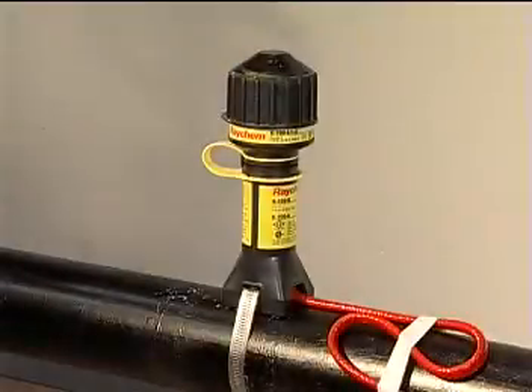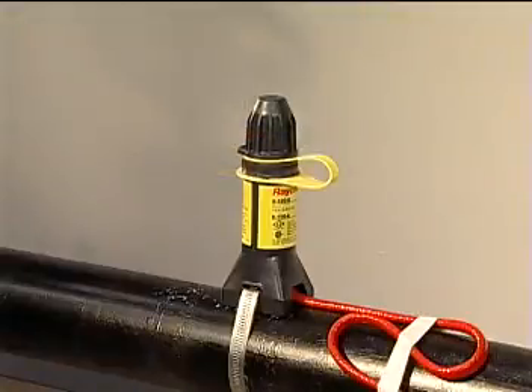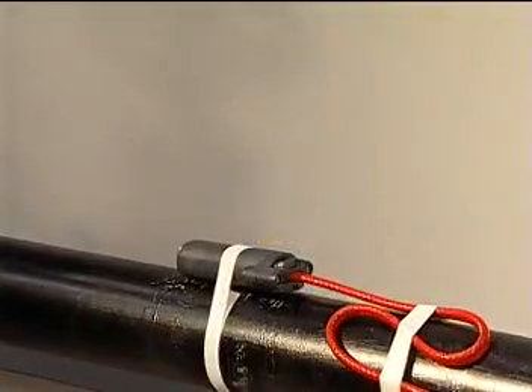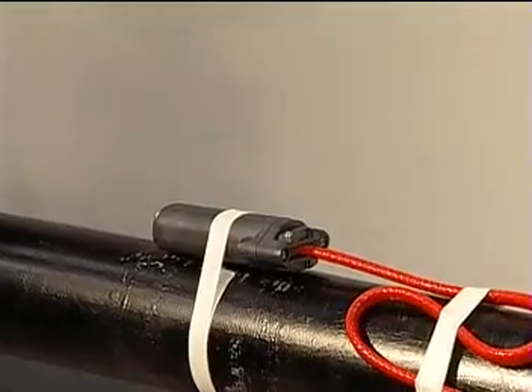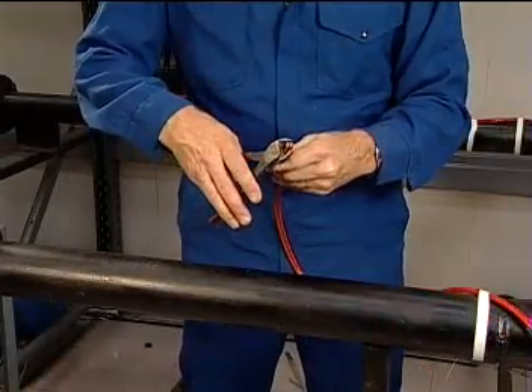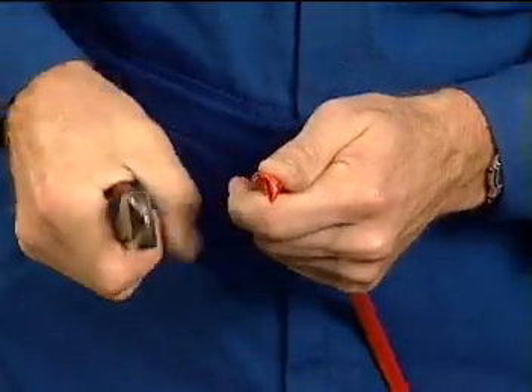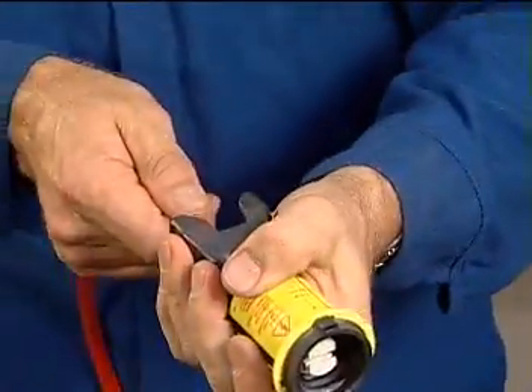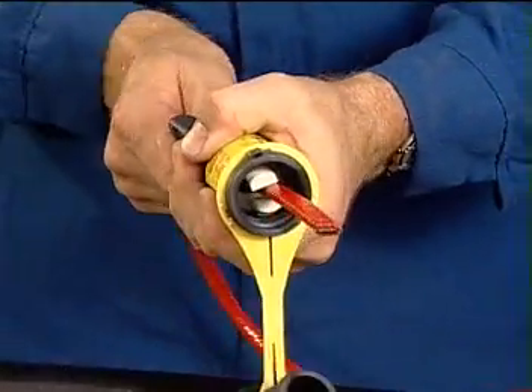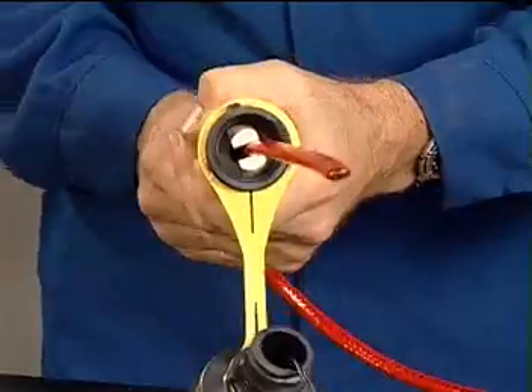Use an end seal to terminate a cable at the end of a circuit. There are 3 types available. Also, preparing the cable for an end seal is a bit different than other connections. To install the E100L end seal, cut the cable end at a 45-degree angle and insert it into the base, leaving 12 inches of cable exposed.